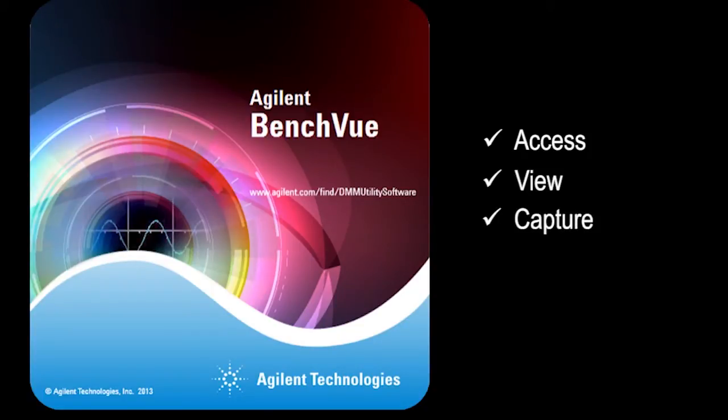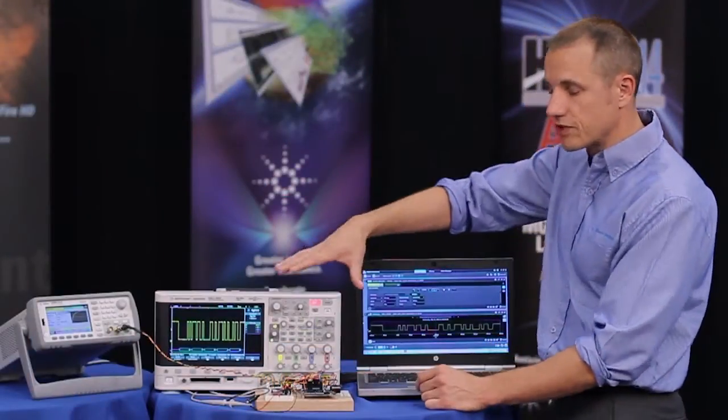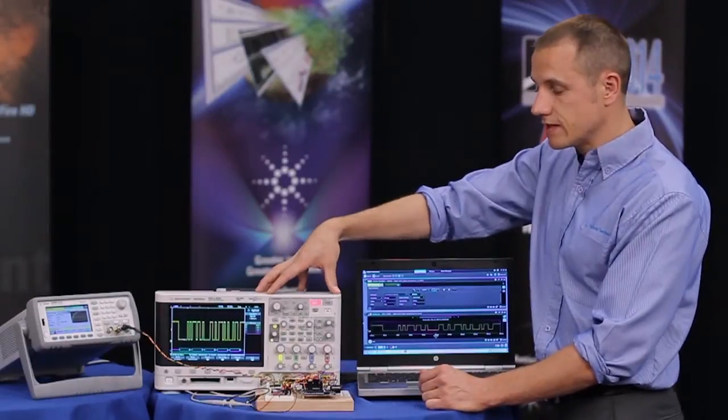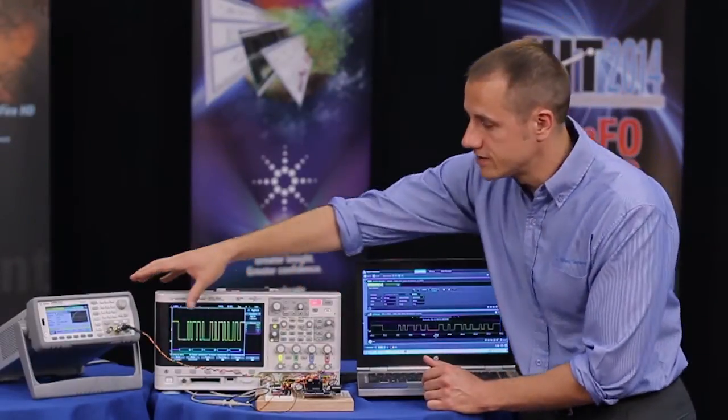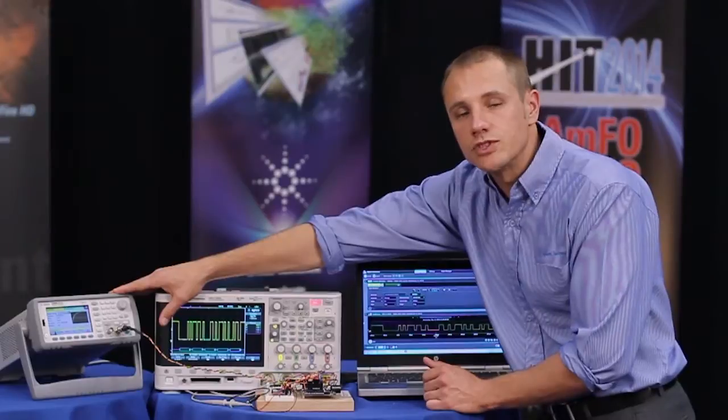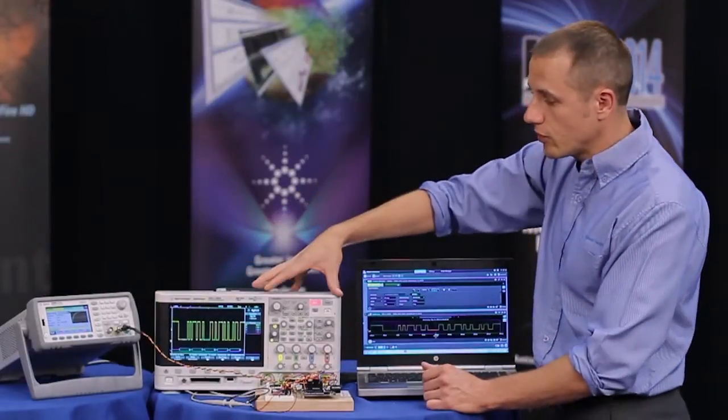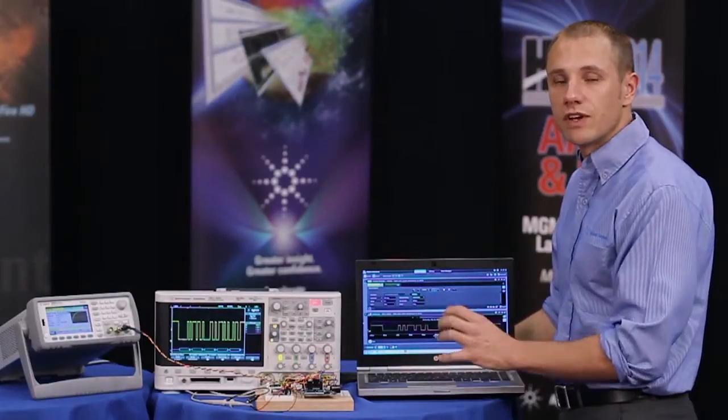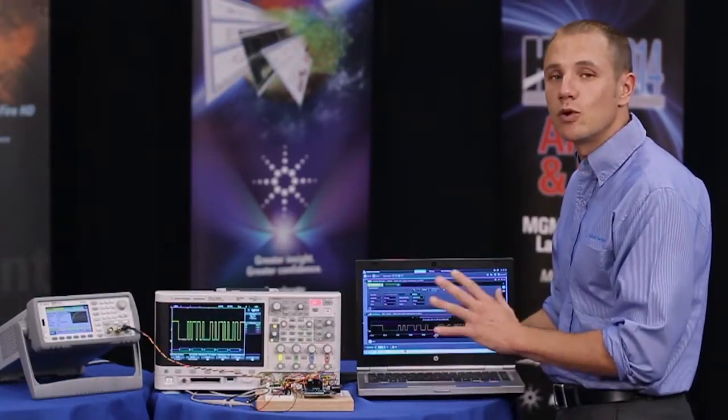Let's take a look at our setup. We have a DUT and we're measuring a digital communication signal from our DUT. Now we want to take the signal from our scope and simulate it on an arbitrary waveform generator. We have both of these instruments connected to BenchVue. So let's take a look at the BenchVue interface and see how we can do this with a simple drag and drop.